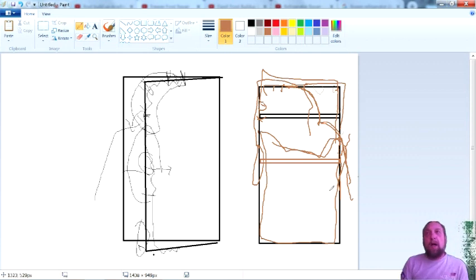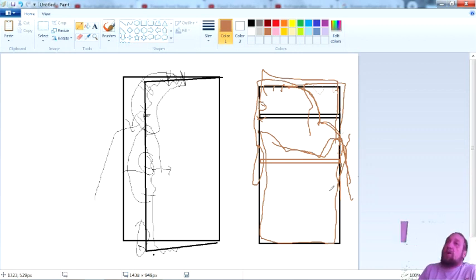Now, why do we do it pieces at a time? Why can't I just take all the screws off, take the old gasket off, put the new gasket on? Why do you want to do it in pieces? Because if you take off the gasket all at once, it'll warp, just like the guy's refrigerator gasket that we saw. You saw how the gasket was warped and not sealing at the top or at the bottom.